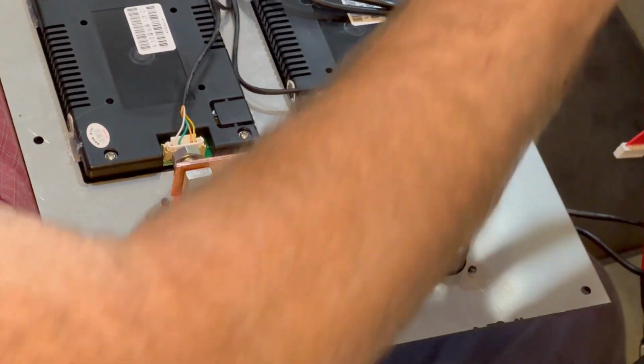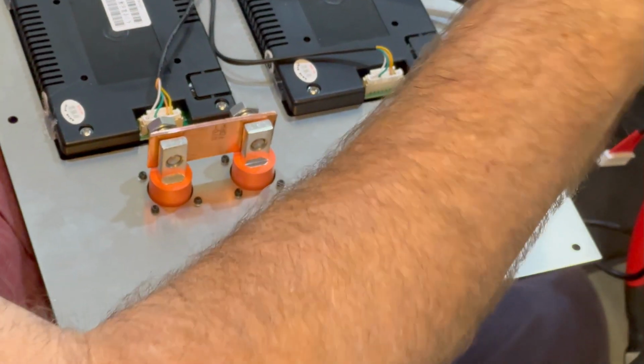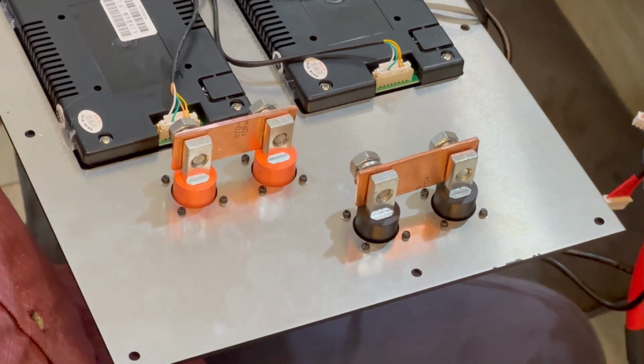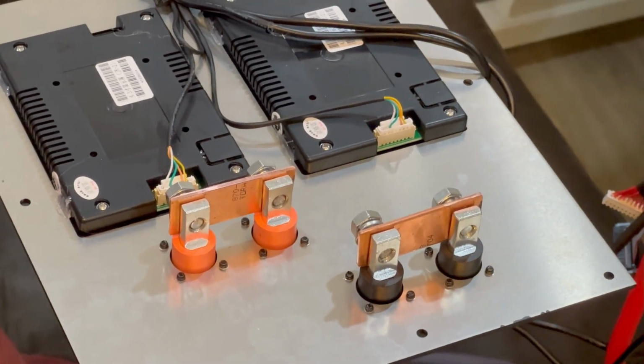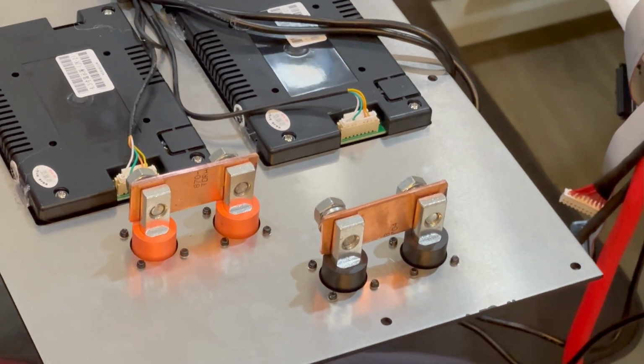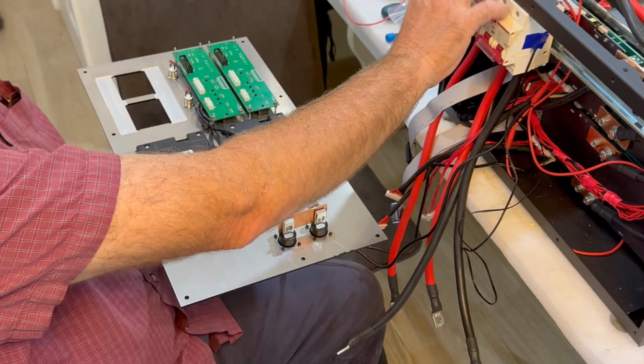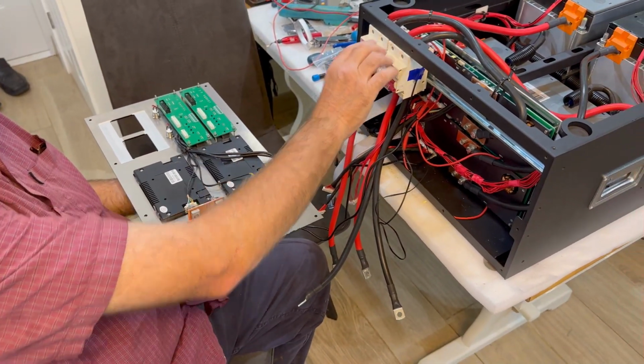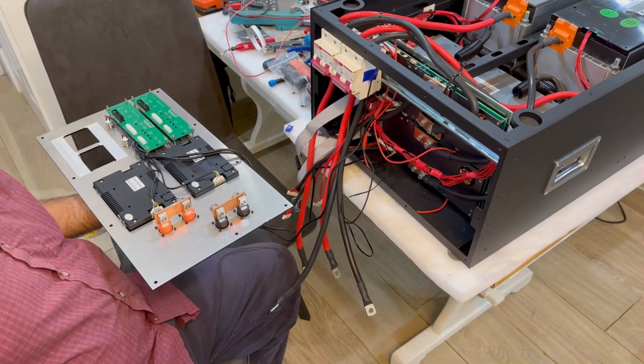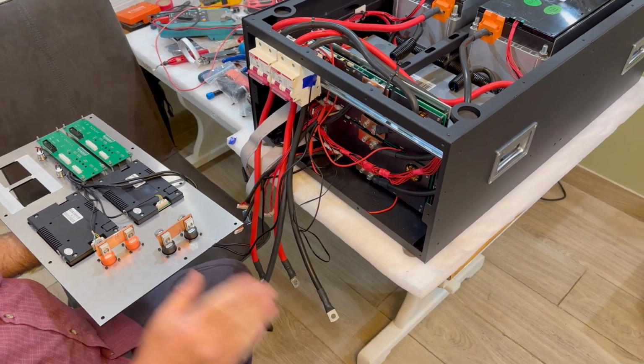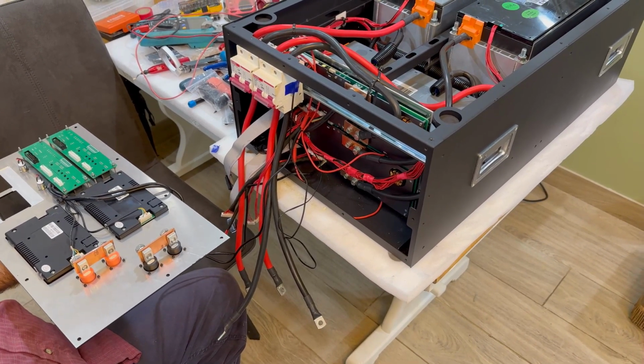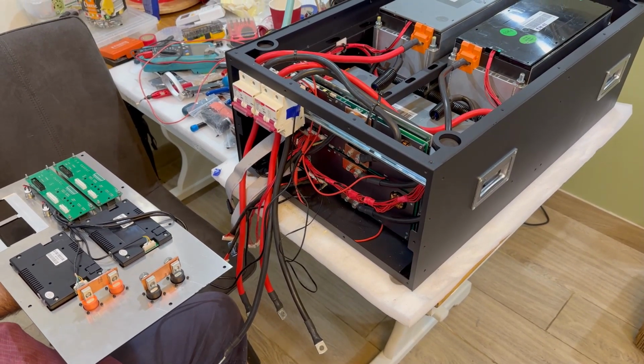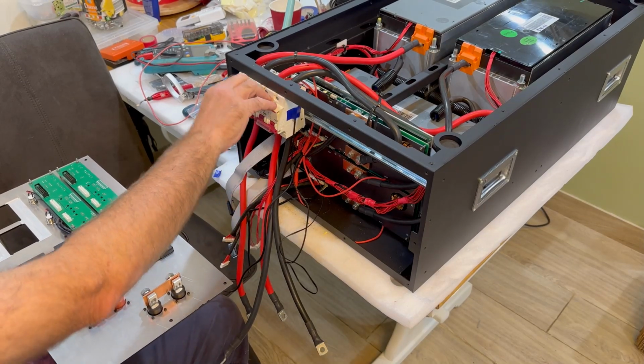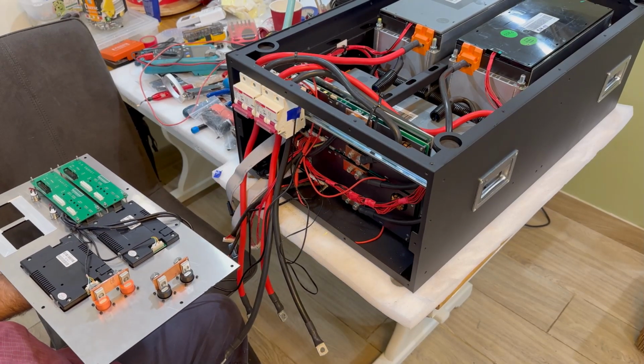I limit the battery to 125 amps, with 125 amp circuit breakers on them, and I tell the BMS that the normal running current is a maximum of 125 amps. These are more purely there for isolation rather than acting as a circuit breaker - the BMS is normally a damn sight quicker. If there's a fault, the BMS will normally turn it off. These are just there so you can actually isolate things yourself.